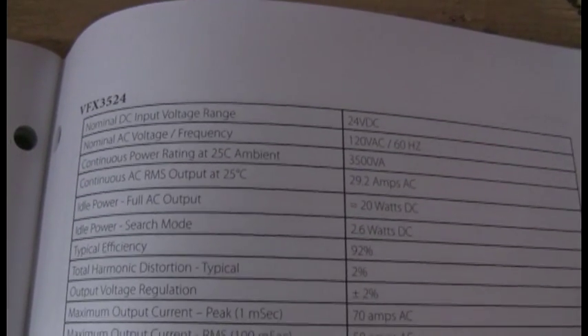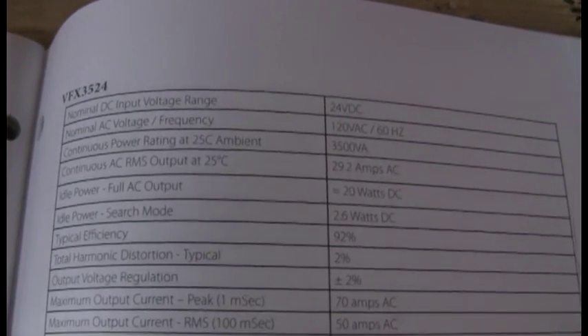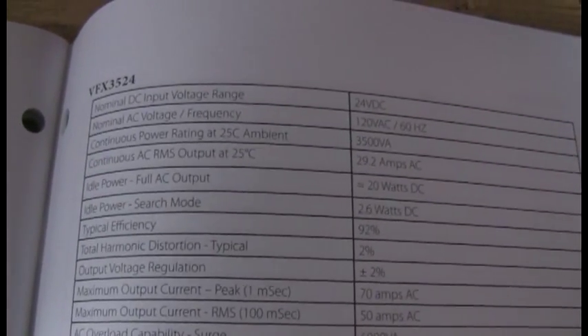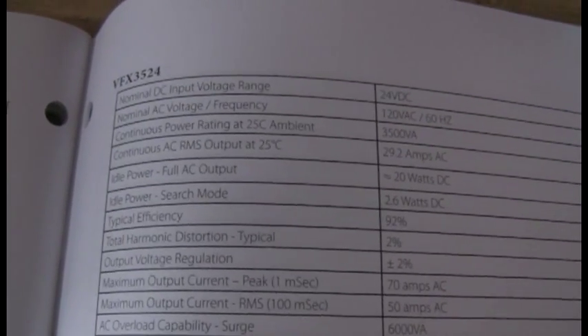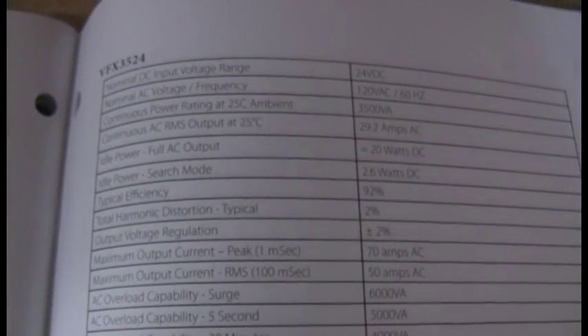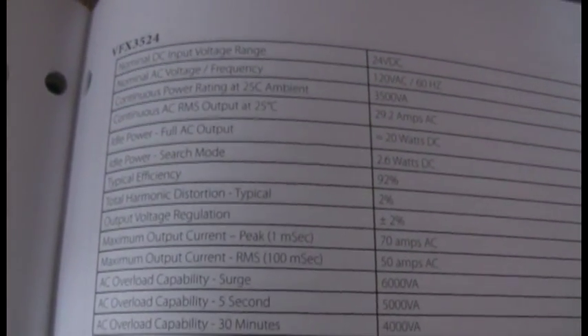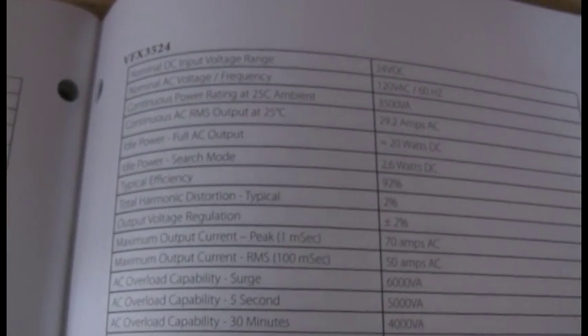Continuous power rating at 25 degrees Celsius ambient is 3500 volt-amps, which basically means 3500 watts or 3.5 kilowatts continuous. That's occurring at about 29.2 amps on the AC side. An interesting one is idle power—how much the unit consumes when standing by.